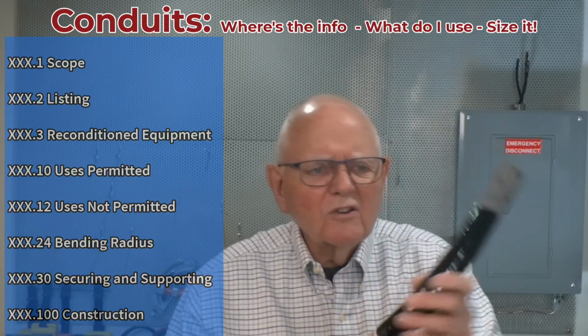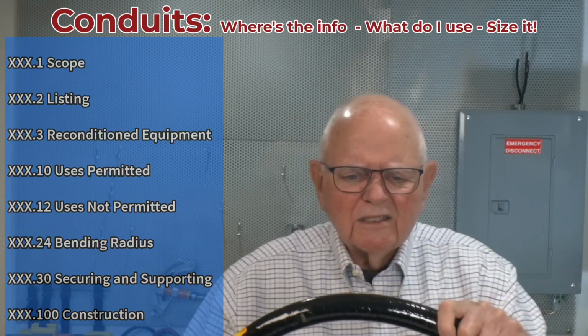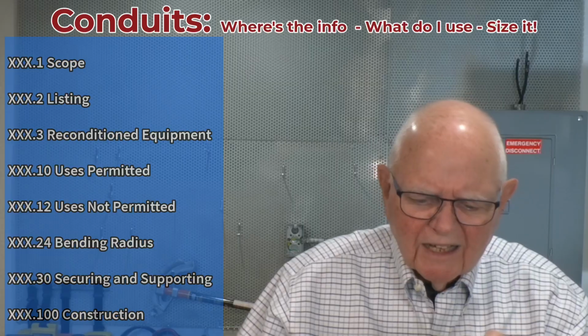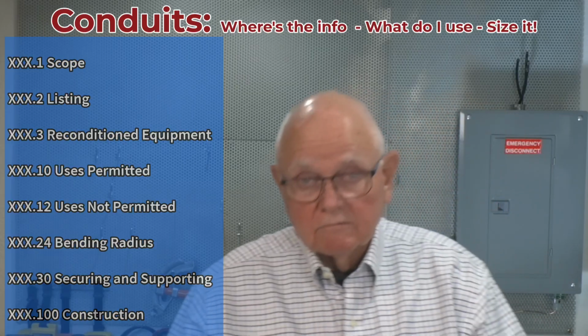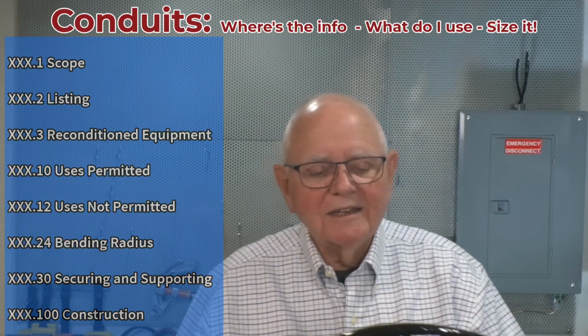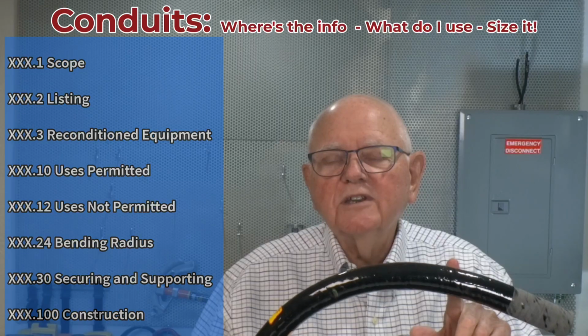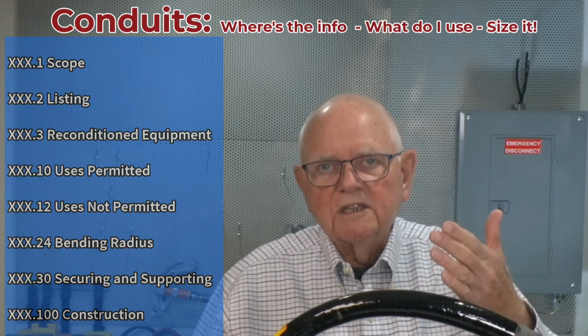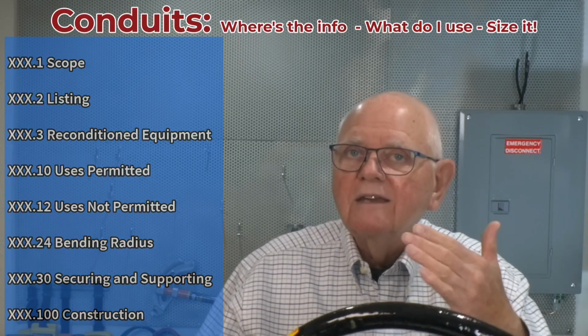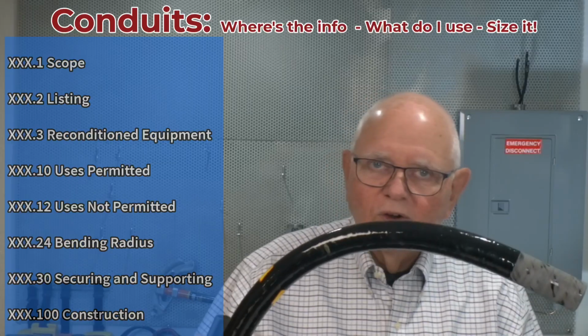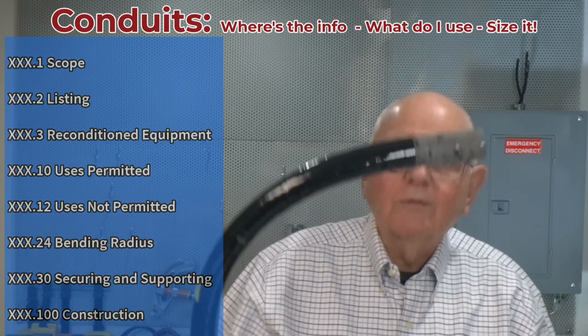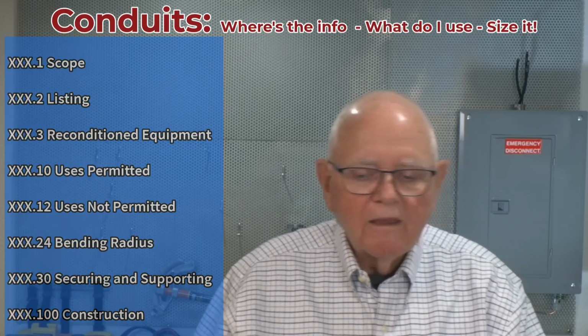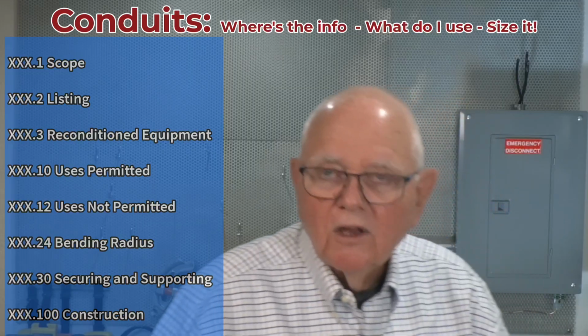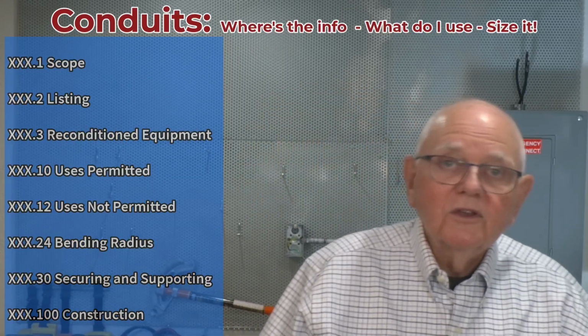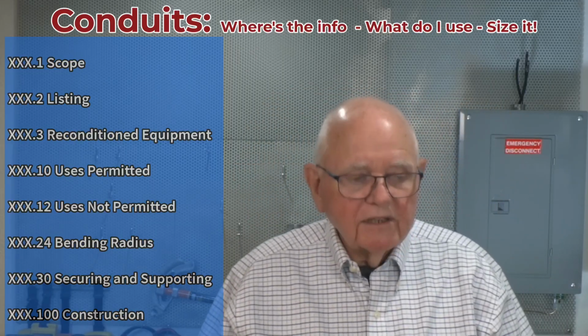Can I put that underground? Can I just direct bury this stuff? I mean, it's fiberglass, I guess, I don't know. Well, you go take a look. You look up the article for RTRC type conduit, look in dot 10 and dot 12. And yeah, in dot 10, it's going to tell you I can go ahead and direct bury a fiberglass conduit and so forth. Anyway, so that's how you determine then what types of conduit you can use where. Look at dot 10 and dot 12.